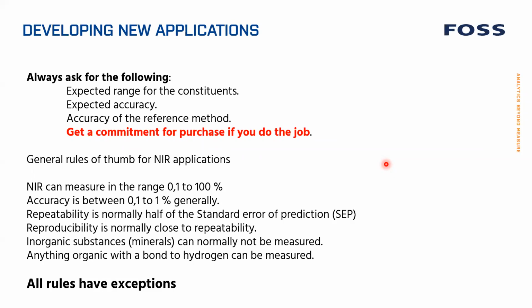Then there are some general rules of thumb for the applications. We can normally measure from 0.1 to 100%, whatever it is you want to measure. Accuracy is normally between 0.1 and 1%. Repeatability is normally half of the standard error of prediction. Reproducibility is normally close to the repeatability.